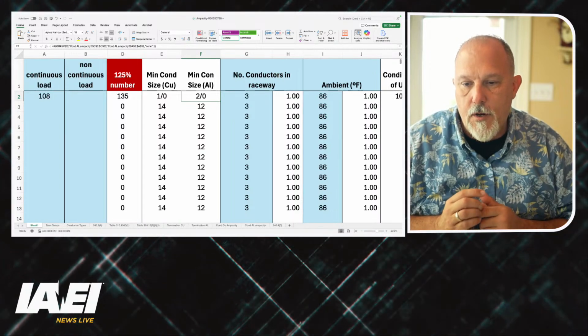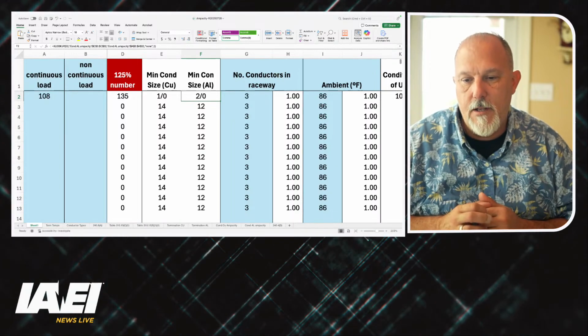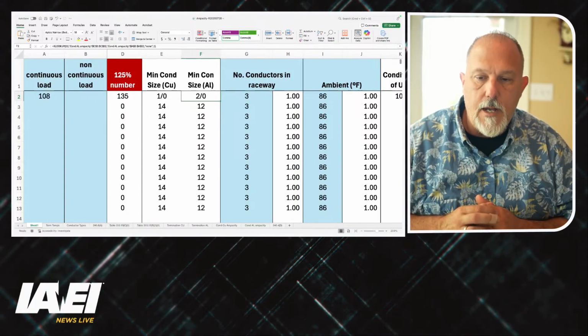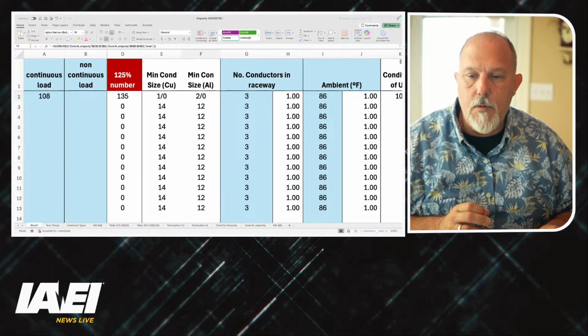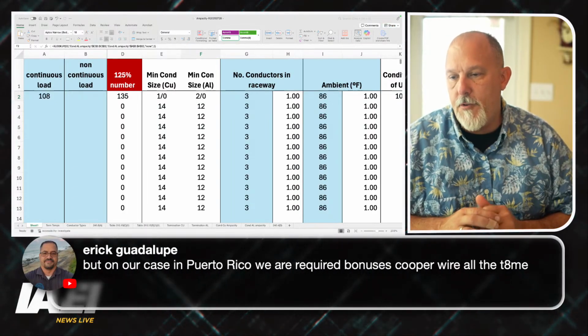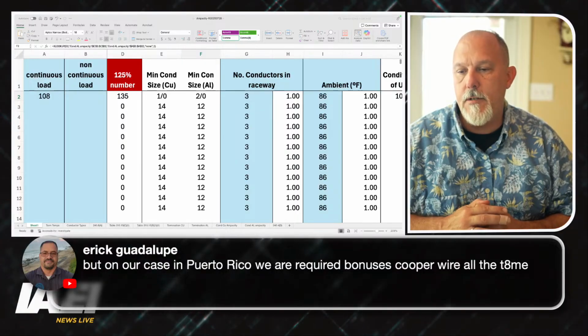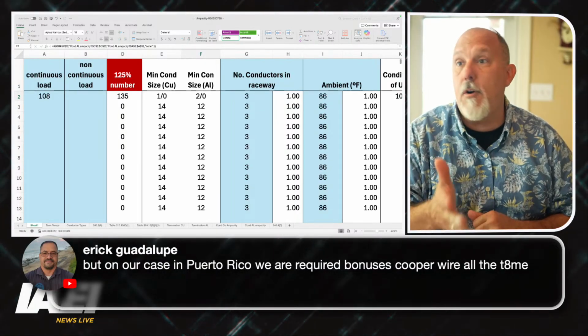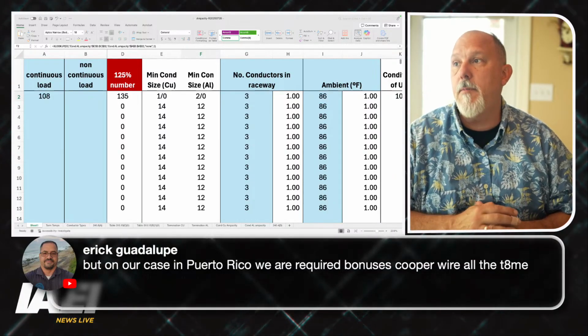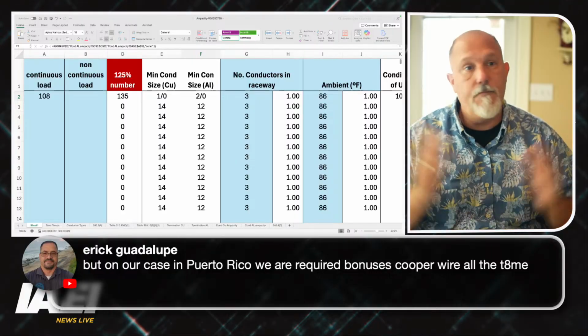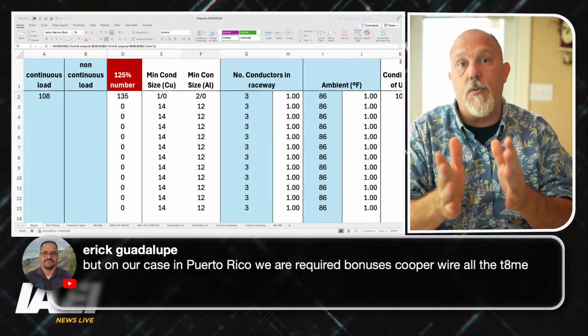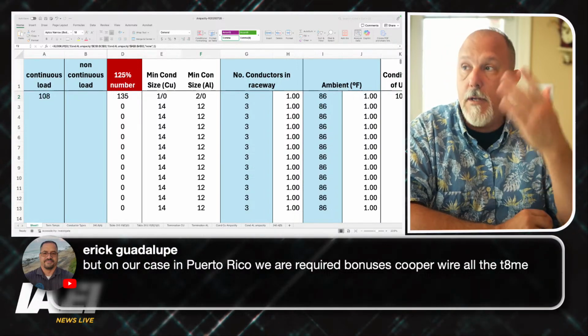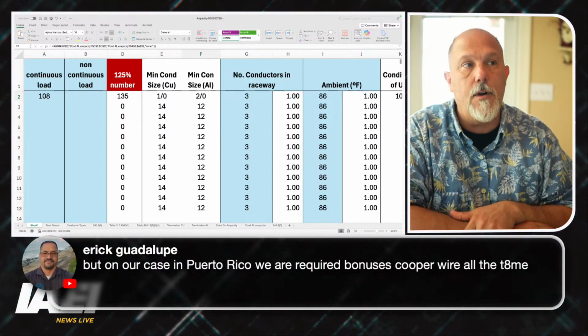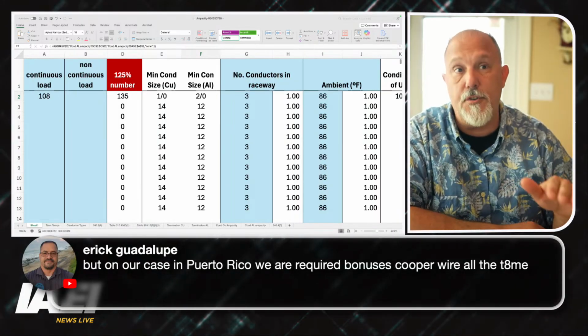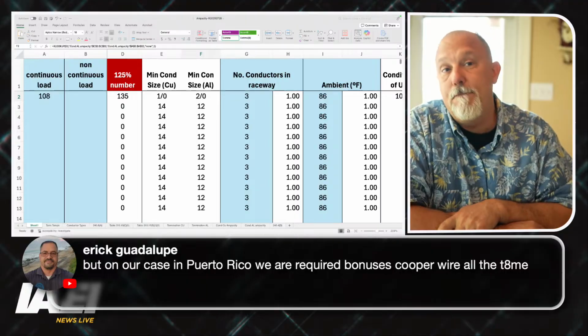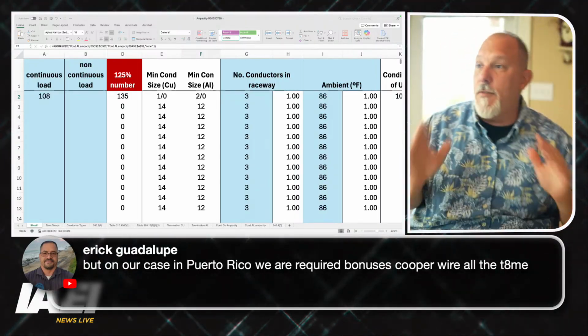But in your case in Puerto Rico, we are required to use copper wire all the time. So if you're using copper all the time, then yes, your minimum conductor size would be a 1-aught copper. Perfectly fine. And that is your preference, that's your choice. And if you have a local law that states it has to be copper, then you're good with a 1-aught. If you are a design engineering firm and you say, look, all we're going to use is copper conductors, 1-aught, regardless, it's a 1-aught. All right, so that's your minimum size.